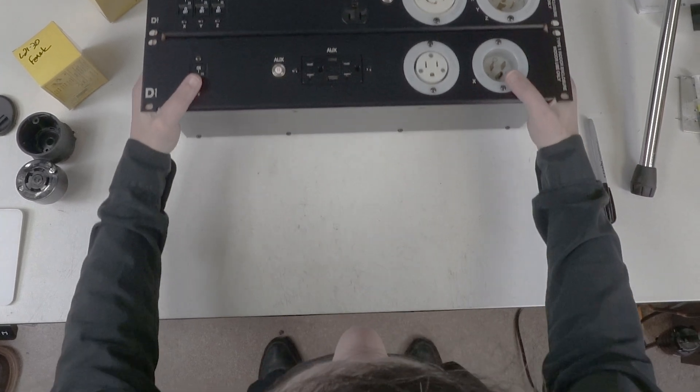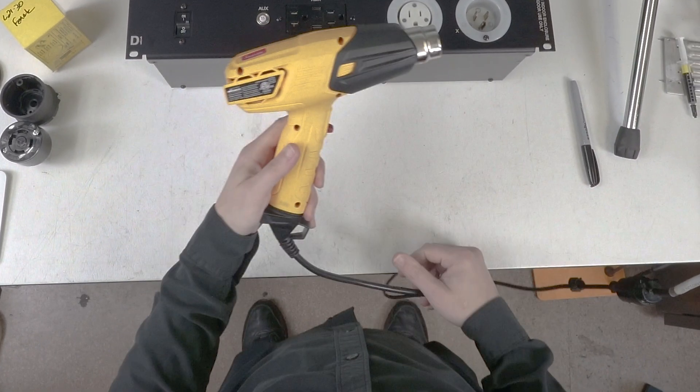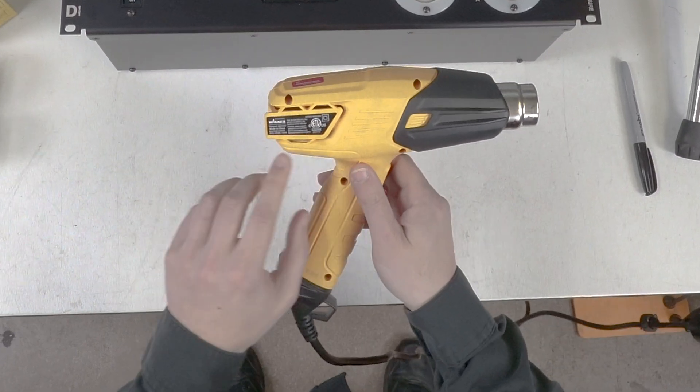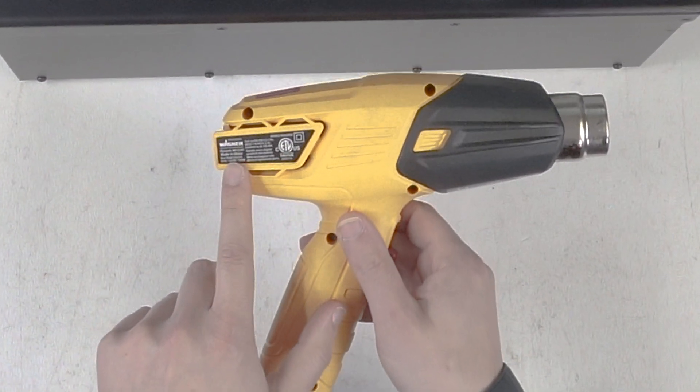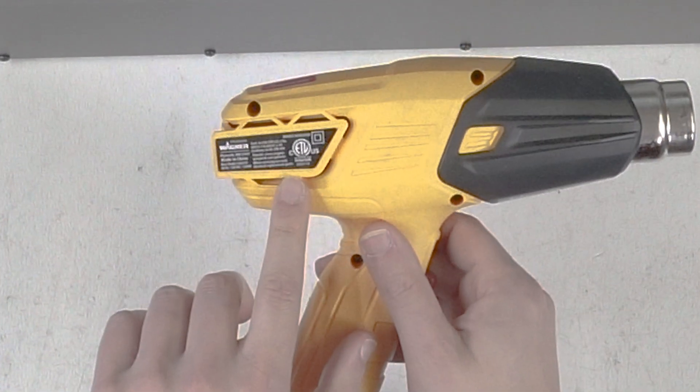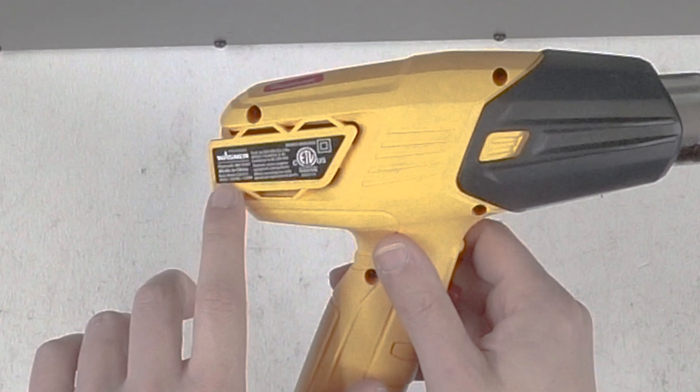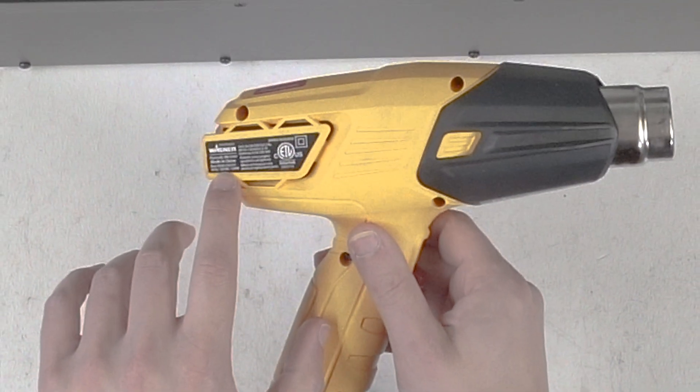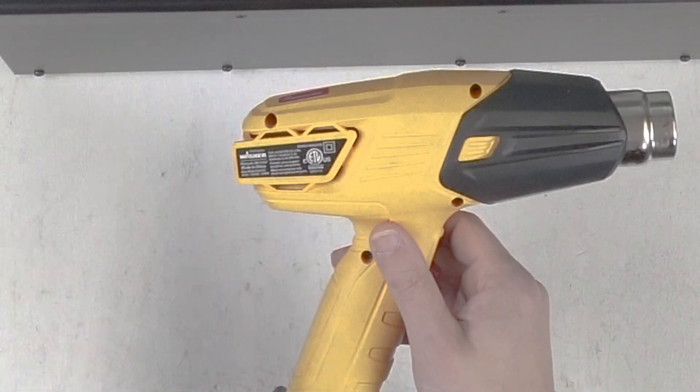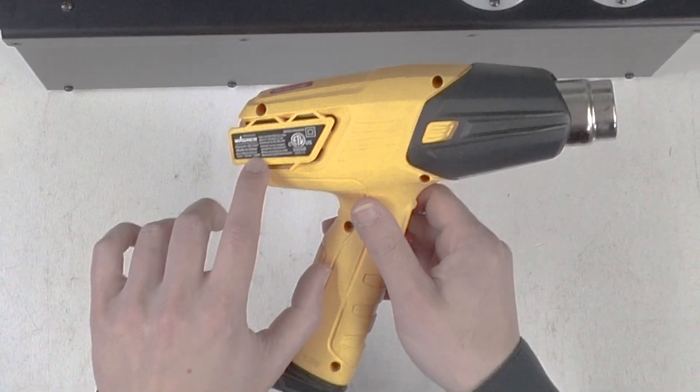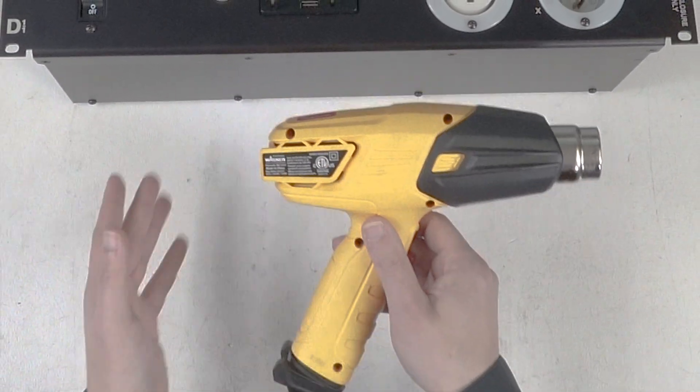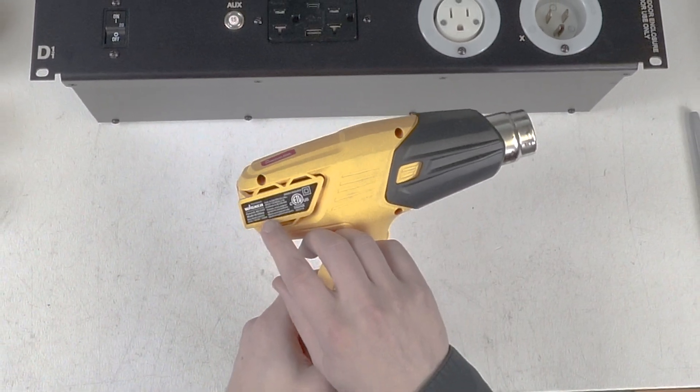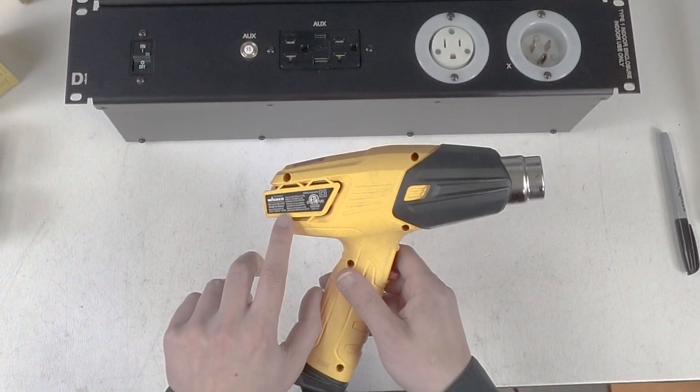Now in calculating equipment, let's use our shop heat gun as an example. Any piece of electronic equipment is going to have a label on the back that tells you what it needs to be powered on. This particular gun requires 60 Hertz power, which is fine because we're in North America. It requires 120 volts AC, again fine for America, and it draws 1200 watts. The easiest way to figure out amperage if it gives you watts is: divide your watts by your voltage. So if we take 1200 and divide that by 120, we know that our heat gun draws 10 amps.